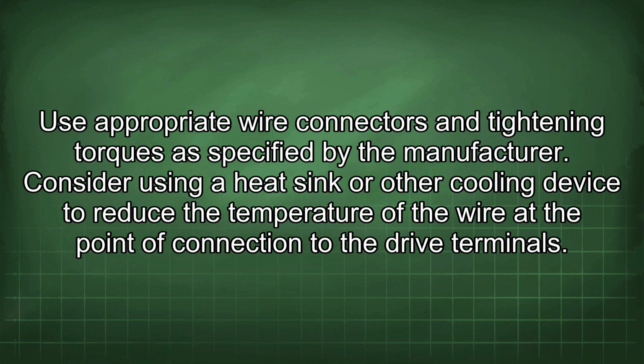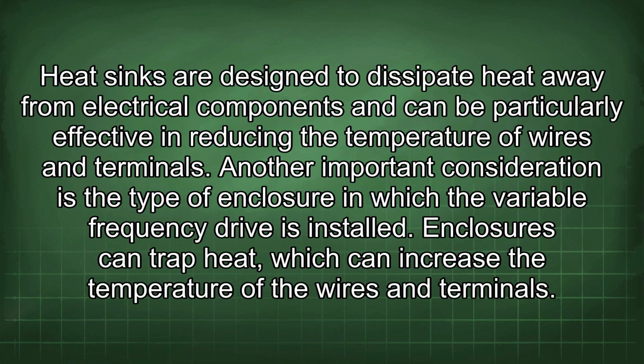Consider using a heat sink or other cooling device to reduce the temperature of the wire at the point of connection to the drive terminals. Heat sinks are designed to dissipate heat away from electrical components and can be particularly effective in reducing the temperature of wires and terminals. Another important consideration is the type of enclosure in which the variable frequency drive is installed.